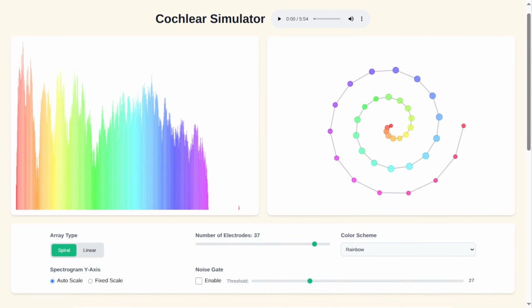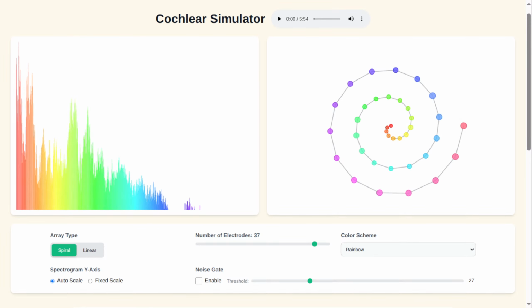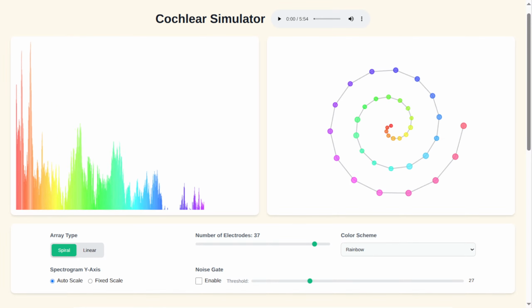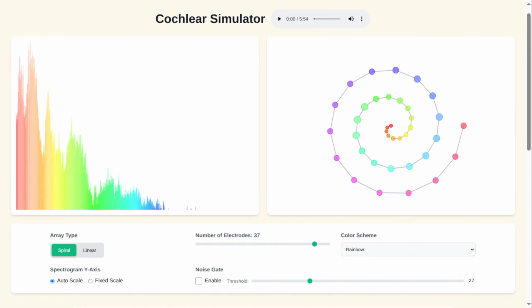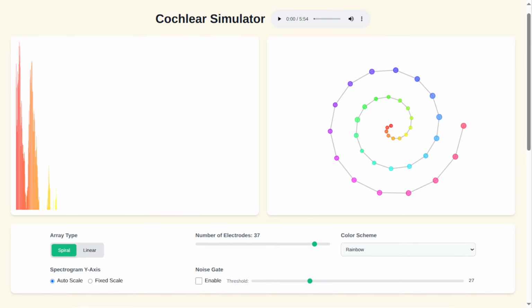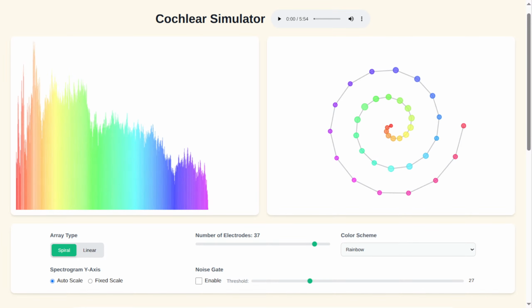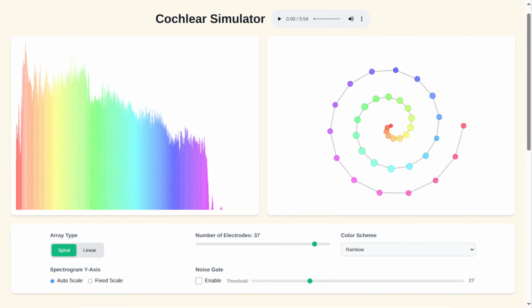Then there's another feature, frequency compression, or FC. Okay, what's that one? That's where the hearing aid shifts higher frequency sounds, which someone might not be able to hear, down into a lower, more audible frequency range. Trying to make those sounds accessible again? Precisely. But interestingly, a study that used what they call clinically realistic settings, so not extreme settings, with start frequencies above 4 kilohertz, actually found no effect of FC on preference or signal fidelity. Oh, so it didn't help or hurt in that case. In that specific, more realistic setting, yes. Which kind of goes against what you might expect if you're using more aggressive, lower starting frequencies for the compression. It really highlights how nuanced this fine-tuning has to be. Wow.